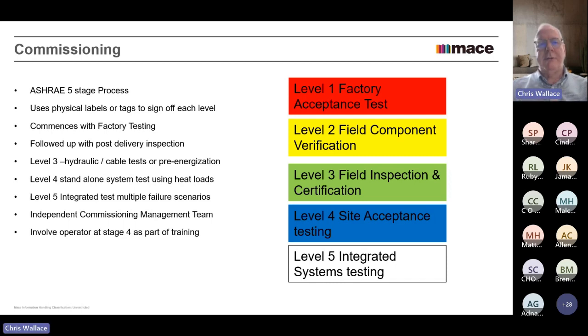And quite often, a number of the customers that we work with will use a physical label on every bit of equipment. So they may follow this color scheme, and you may actually go to a piece of equipment and say, right, it's got no level three green tag on it, we can't power it up. And then, once it has a level three test green tag on it, we've powered it up, we'll now test it locally. And then level five will be when we test it as the whole thing together.